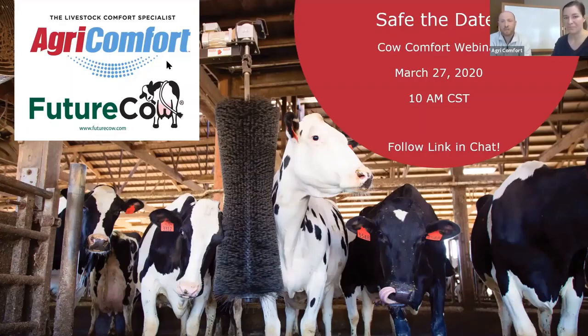Yeah, so you've probably asked the hardest question of all of the questions that we're probably going to get today. The idea of using fresh outside air, which we saw from that research, showed that we have to go outside to get that low bacteria, low contamination air. Then the problem is it's going to come with some bad things. Sometimes it comes with extra heat, sometimes it comes with a lot of cold, but the worst is it comes with humidity. And so how do you deal with that humidity? That's by far the hardest part of ventilation, is that unless we're willing to pre-treat the air when it comes in, we're stuck with dealing with what it brings in the way it is.